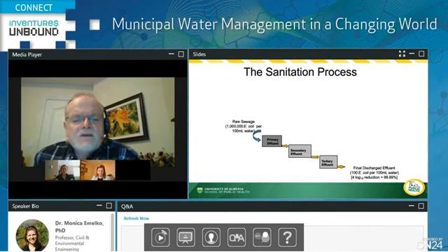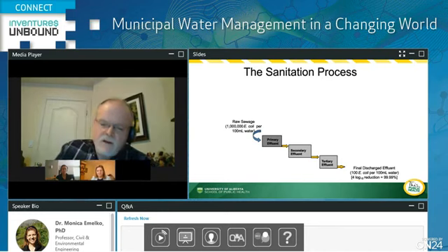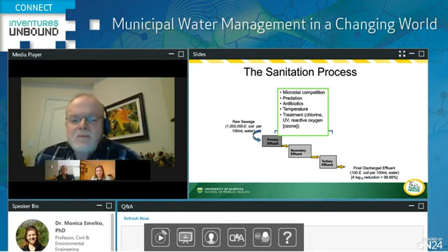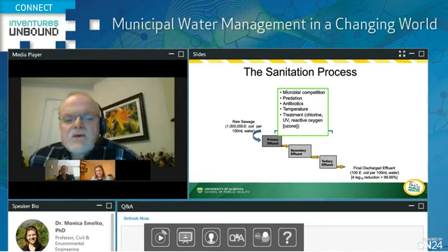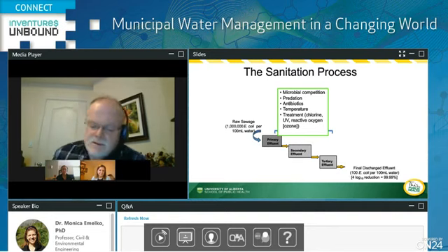When it comes into the sewage treatment plant, you'll have a concentration of E. coli of about 1 million E. coli per 100 mLs of water. And we put this through a series of different treatments that are there. And the final discharged effluent is typically around 100 E. coli. So we move from about 1 million E. coli to 100 E. coli, and we have a 4-log reduction across that process, which, as Monica's talked about, is equivalent to a 99.99% reduction in E. coli.